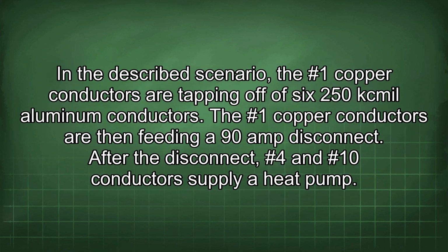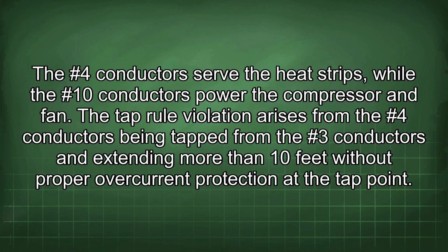In the described scenario, the #1 copper conductors are tapping off of 6 250 kcmil aluminum conductors. The #1 copper conductors are then feeding a 90-amp disconnect. After the disconnect, #4 and #10 conductors supply a heat pump. The #4 conductors serve the heat strips, while the #10 conductors power the compressor and fan. The tap rule violation arises from the #4 conductors being tapped from the #3 conductors and extending more than 10 feet without proper overcurrent protection at the tap point.